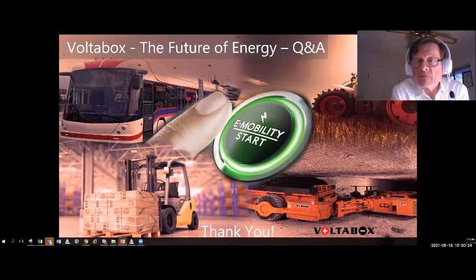And then you have things like water. You can use water on a car fire, and you see it all the time. And then you read that the electric car caught on fire, the battery was on fire, the fire department came, they put the fire out, and they left, and the car caught on fire again. And they came back and put the fire out, and the car caught on fire again. This goes on and on until you get to the root cause. So the water doesn't put the fire out. What it does is stop the propagation. It's a mitigation element to stop the propagation from cell to cell. So it is a very important issue, very much part of the industry playbook to improve safety.